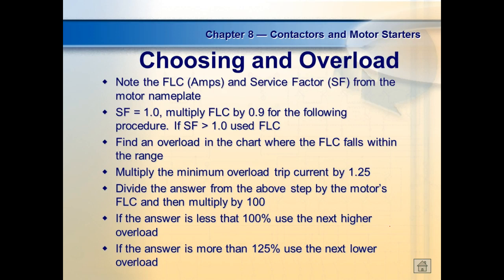Everybody okay? Then what we're going to do is, NEC understands things happen. So they allow a 25% increase of what you actually calculate. We take that full load current and multiply it by 1.25. So that heater is not only designed for a service factor of greater than one, it's also designed for 125% current, 25% more current. And that's what NEC allows.